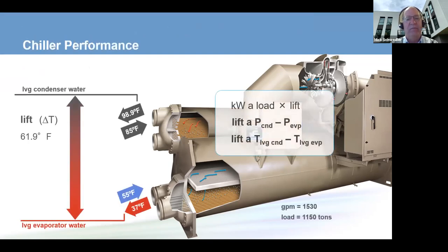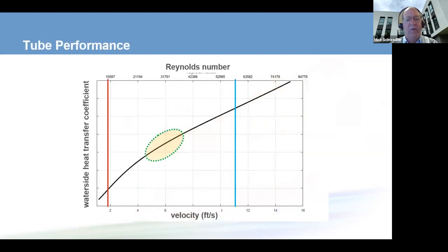From a performance standpoint, the work that a compressor has to do is proportional to the load, in this case, 1,150 tons. And then that pressure differential between the evaporator refrigerant pressure and the condenser refrigerant pressure. Those are proportional to the leaving condenser water temperature minus the leaving evaporator water temperature. In this case, a 62 degree lift. Okay. And what we want to do, we want to get good tube performance. We want to stay in this region where we have good heat transfer. So generally, if we stay above 1.5 to 2 feet per second, depending on the tube type, we are going to maintain that good supply water temperature control, the good heat transfer, and the good efficiency.